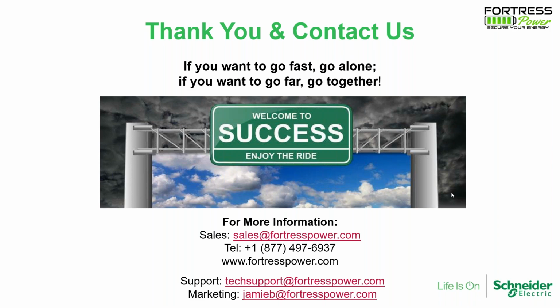That's what we call open voltage control. We typically see, if you add the 0.0, it's more academic. If you charge your capacity at like 0.5 C or 0.6 in that range, we typically see 54.7 volts is 100%, and then if you come down to 51.3 or 51.4, that's where you see 15 to 25%. So that's the range.